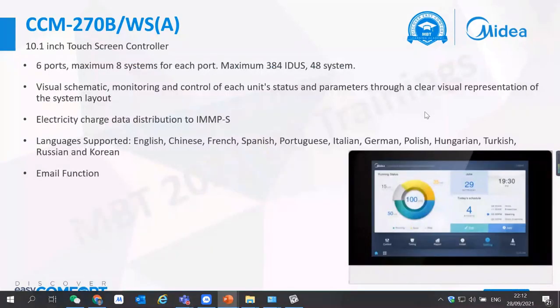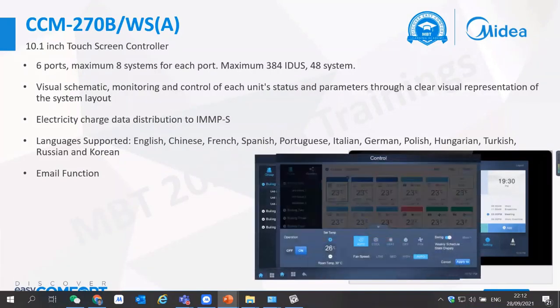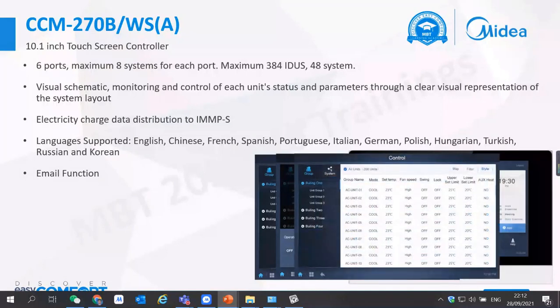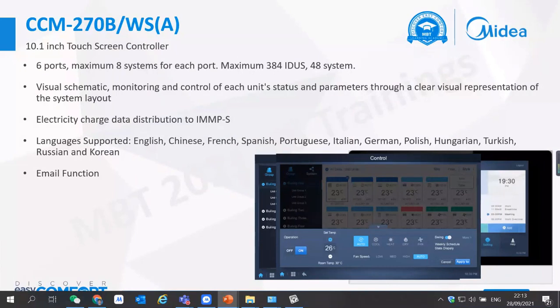Apart from capacity, let me tell you the main improvements - schedule and holiday it can also do. Next is floor plan, you can insert a map inside the controller. I'll show you directly - these are basic settings so I won't repeat them. You can set a group or set the symbol, similarly set the cooling set limit, heating set limit, mode limit, fan speed limit, and lock the wired or wireless controller.